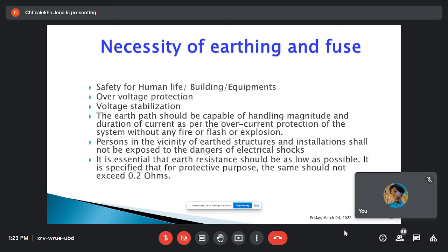So earthing is very important. Persons in the vicinity of earthed structures and installations shall not be exposed to the dangers of electrical shocks - if earthing is proper, the persons will not be exposed to such danger. It is essential that earth resistance should be as low as possible. It is specified that for protective purposes, it should not exceed 0.2 ohms.